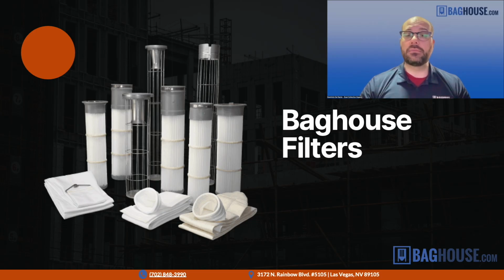then we might go up to something like fiberglass bags, which are more delicate. So we have to take some extra precautions if we use fiberglass bags. For example, we have to use special cages that have extra wires on them for fiberglass. But these could be used on some dryers and kiln applications. We'll have to take some extra precautions.